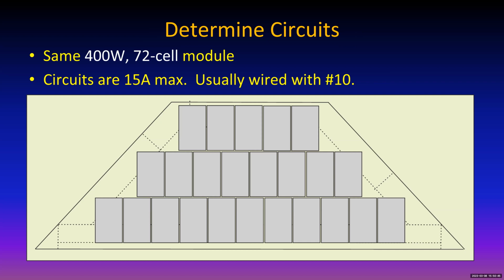optimizers, they're still usually wired with number 10 wire. And PV guys like number 10 because we used to always do that. 15, 20 years ago, the circuits were almost always wired with number 10, even though the outputs of the modules were nowhere near that. The reason was simply less power loss, less energy loss in the wire. And when your modules are $100 a watt, you don't want to lose one drop of electricity. So you use fat wire instead. And that's kind of carried on as a tradition, even though with a 15 amp circuit, you could use number 12.